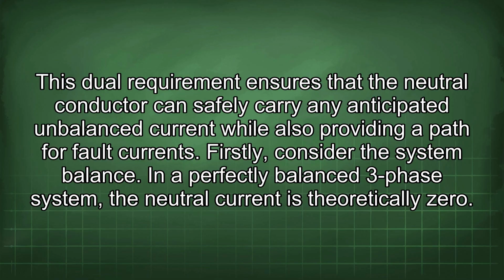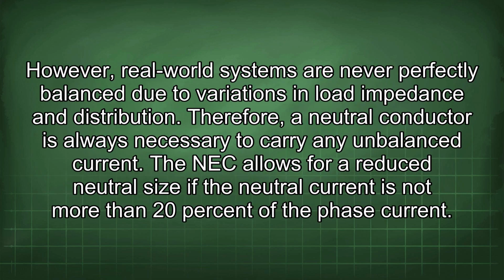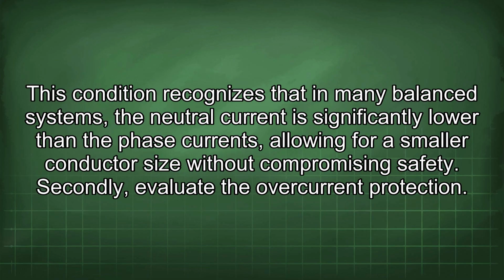In a perfectly balanced 3-phase system, the neutral current is theoretically 0. However, real-world systems are never perfectly balanced due to variations in load impedance and distribution. Therefore, a neutral conductor is always necessary to carry any unbalanced current. The NEC allows for a reduced neutral size if the neutral current is not more than 20% of the phase current. This condition recognizes that in many balanced systems, the neutral current is significantly lower than the phase currents, allowing for a smaller conductor size without compromising safety.